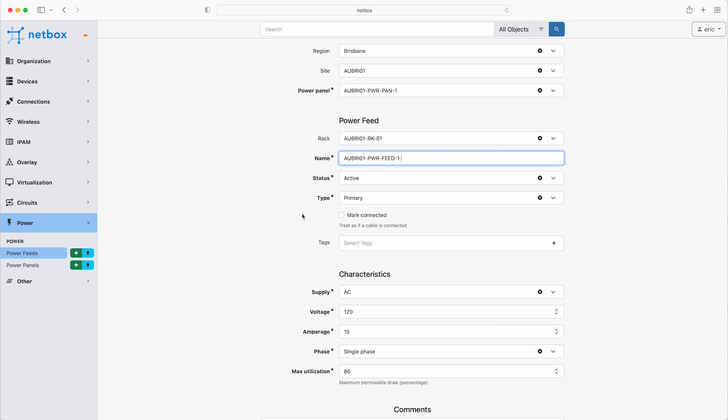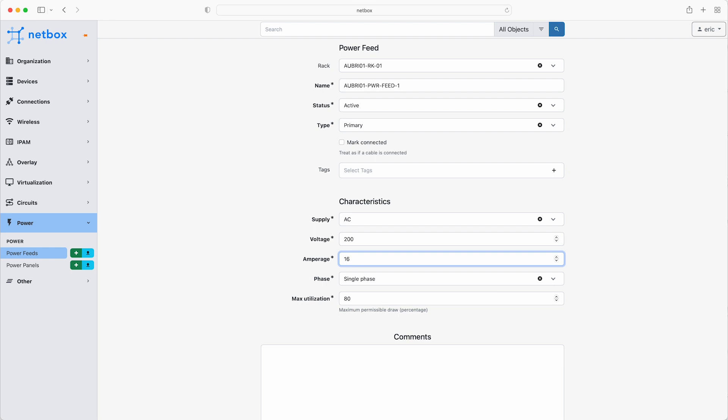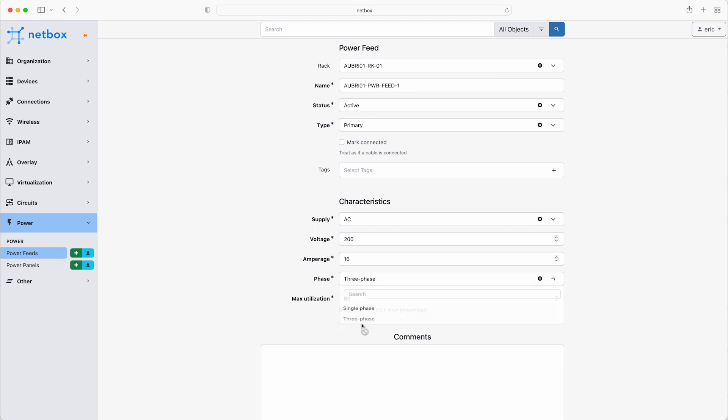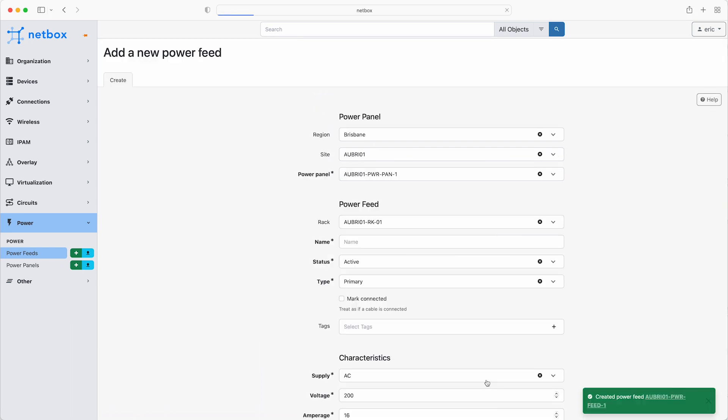Now this feed will be the primary feed, so moving down to the characteristics, the supply is AC, 200 volts, 16 amp, 3 phase. I'll leave the maximum utilisation at 80%, so that we're not at risk of attempting to draw too much power from it. Then click create and add another.